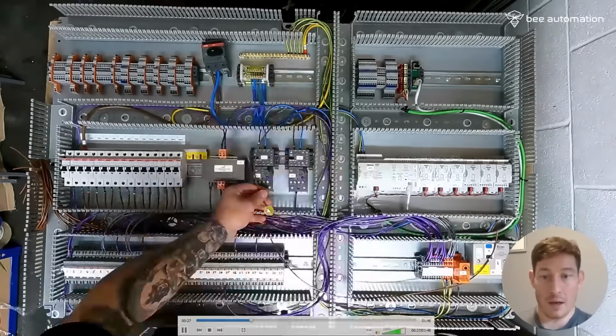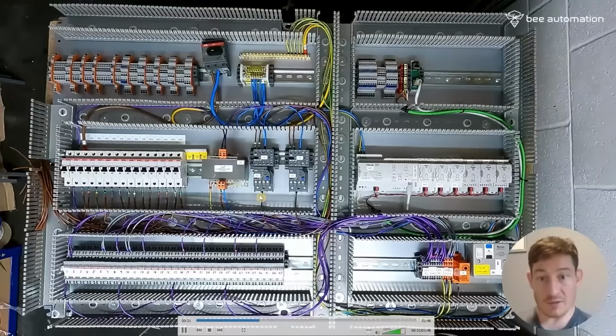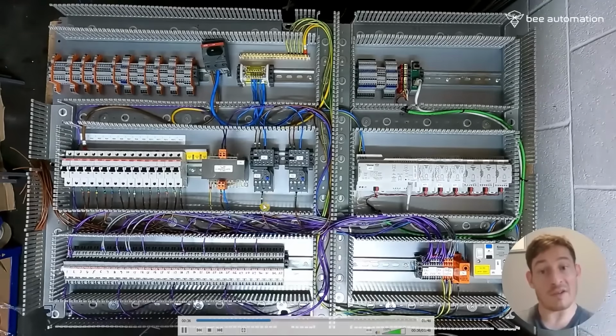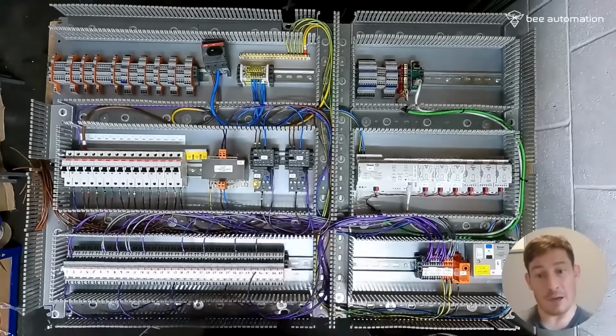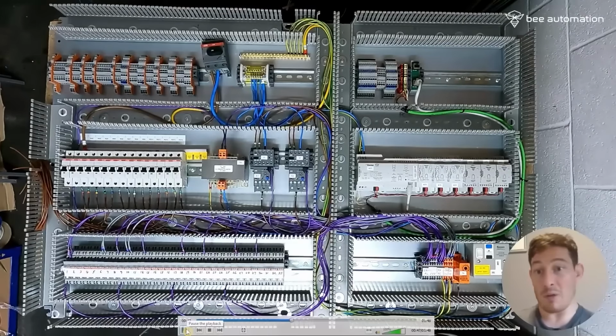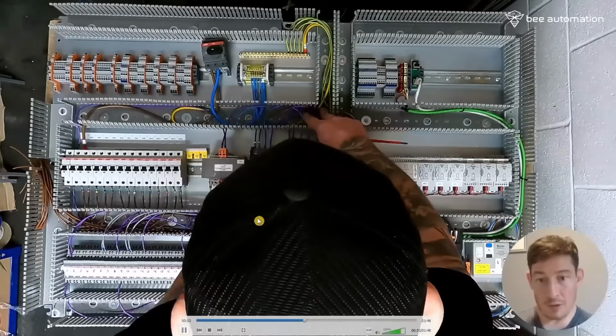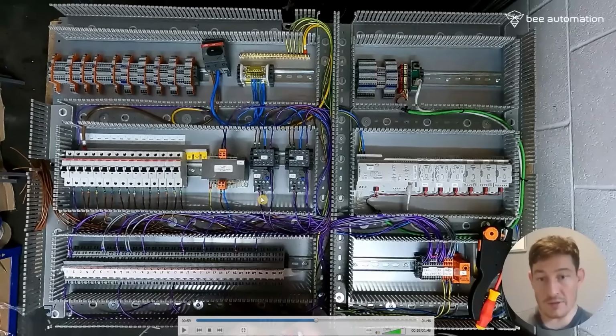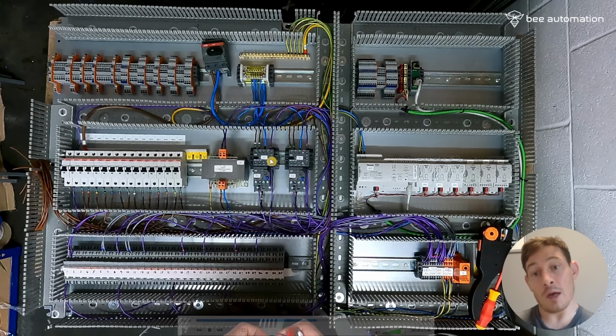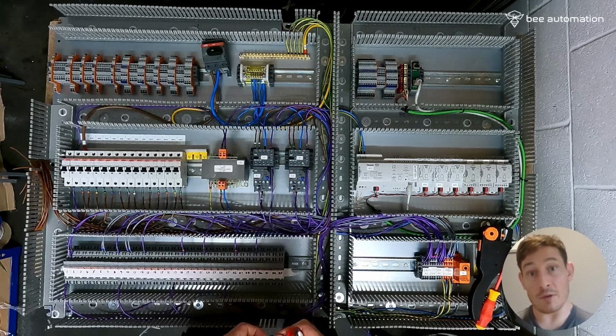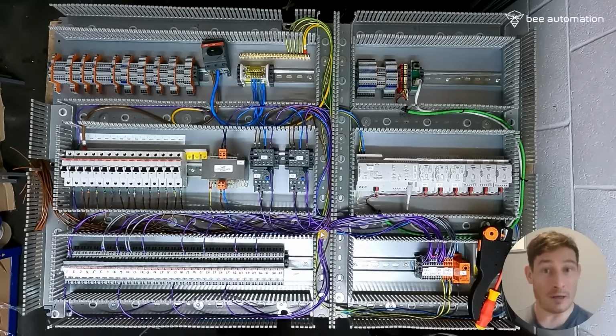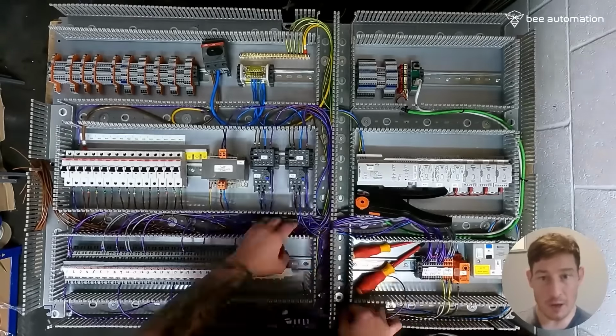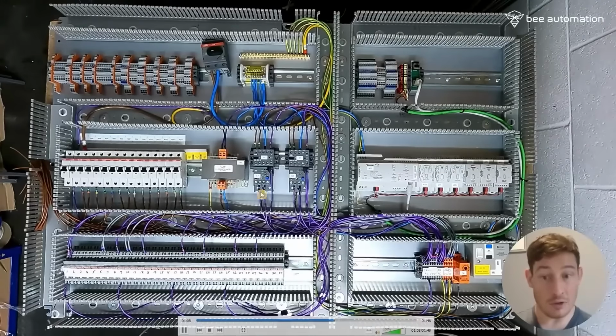And it's important with these overloads that the full load current goes through all of the terminals on the overload. So if it's single phase, you've got to loop it back round so it goes through all 3 phases, which will enable it to trip correctly. This bit I'm just wiring out of one side of the normally closed contact into A1. So that's how you correctly wire an overload relay. It needs to go through the normally closed contact of the overload into the coil A1 terminal of the contactor. So if that trips out, it then cuts out the power going to the coil energizing the contactor. That's really important that you understand that, because I've seen many times people wiring them incorrectly and it can cause major issues, pumps overloading, overheating, potential fires, etc. So it's important you know how to wire these correctly.